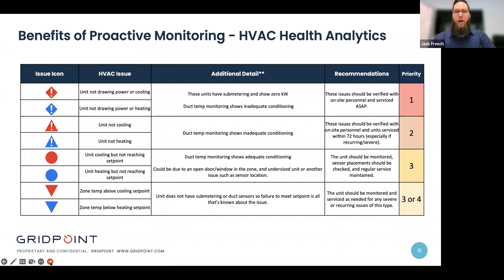Starting at the top, a priority one issue would be for a solution where we have HVAC control, duct temperature sensors, and submetering. So we know how much energy or power demand we're seeing for each individual asset. The top two exceptions that are priority one would be that the unit is not drawing power for cooling, or the same with heating. That means the unit is showing 0 kW on submetering, and the duct temperature is showing that it's not adequate to actually condition the space.